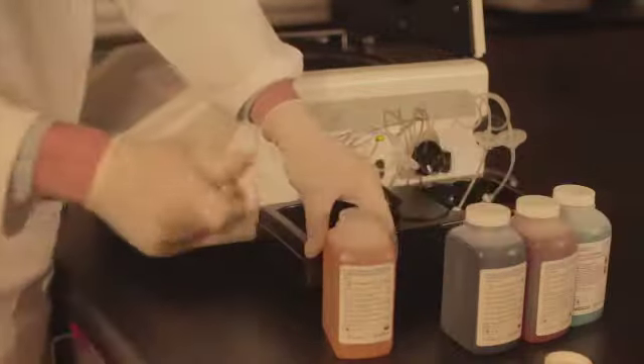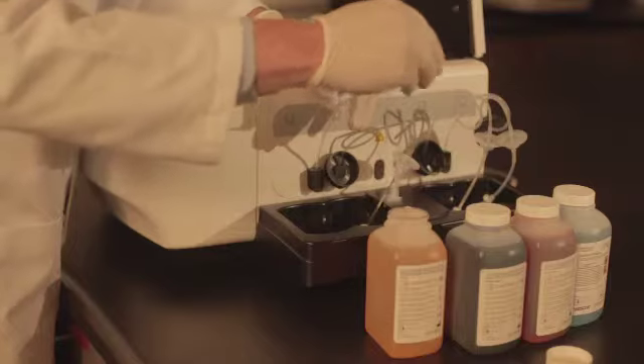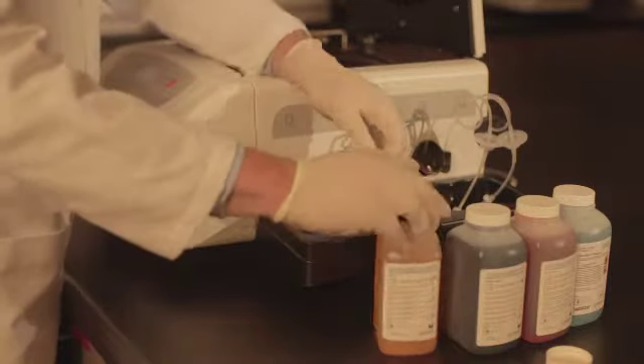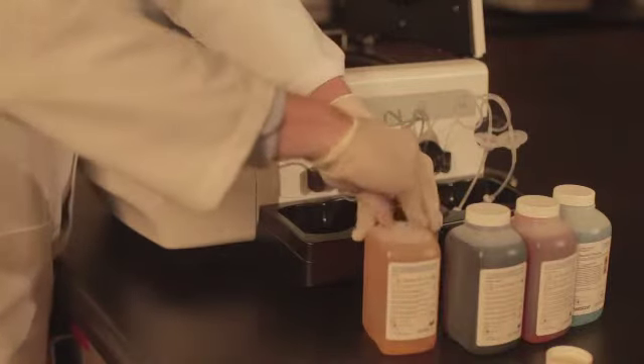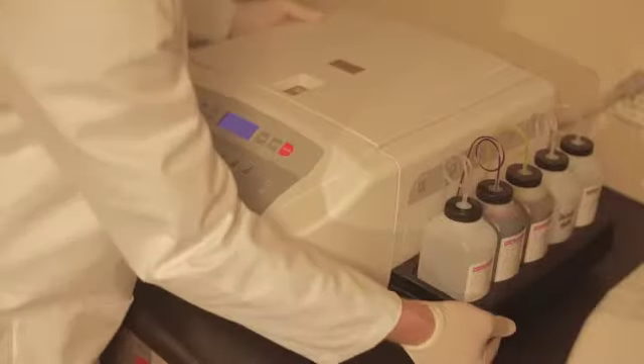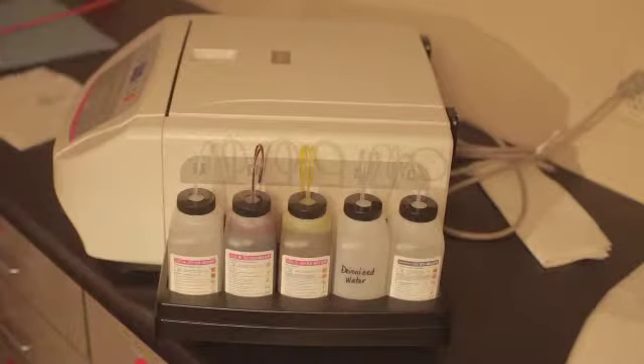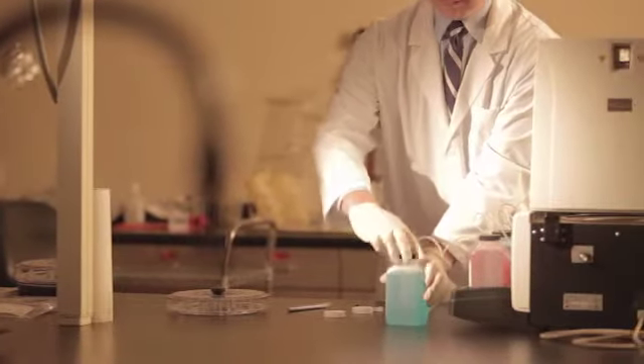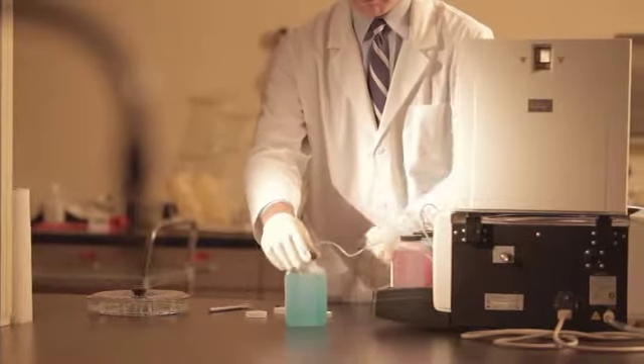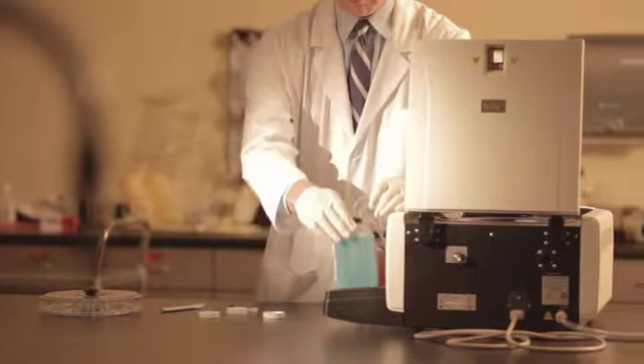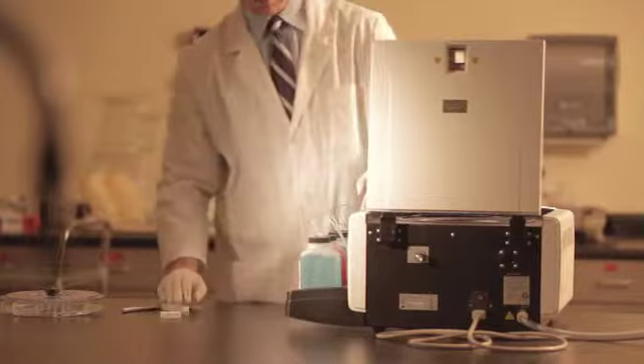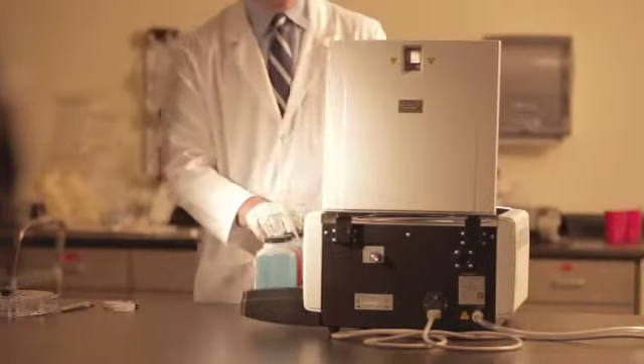Install the bottles on each line by removing the seal from the bottle and placing the dip tube in the bottle. Screw on the lid and make sure the curl stays in a tight curl after the lid is tightened. After the dip tubes have been placed in each respective reagent bottle, it is now a good time to zero the level monitoring sensors. Zeroing the sensor should only have to be done once, unless the stainer is moved to a different spot. It is much like zeroing a sensitive scale.